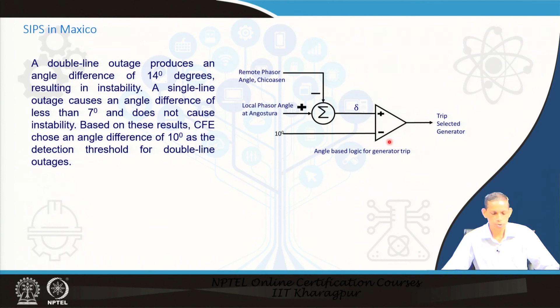So, overall we say that synchronous data from PMUs and relays with GPS facility can be used for different applications. We have real time applications as well as offline applications which are of relevance from the protection perspective, like SIPs for online applications, differential protection and fault identification for zone 3 application perspective, and also offline applications for parameter estimation. But in real time applications, latency is the challenge, the late arrival of data. If that is compatible, the corresponding synchronized data through wide area measurement systems can be a good addition for system level protection, including element level protections, as a backup or supplementary.